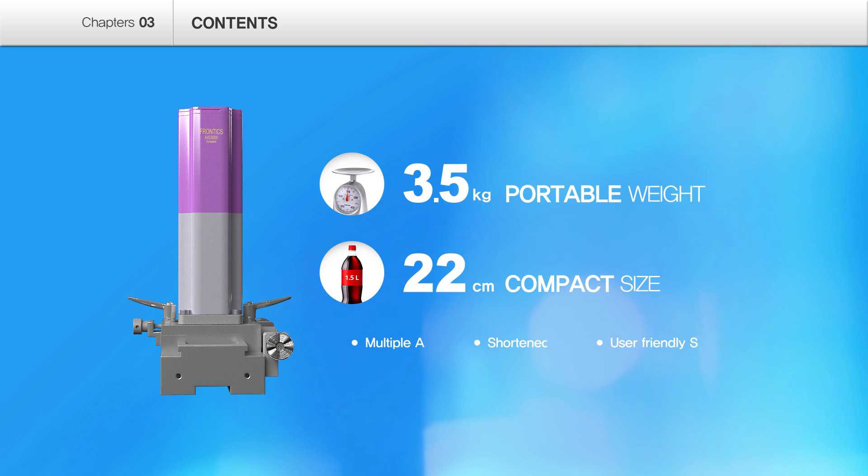AIS 3000 Compact Equipment weighs 3.5 kilograms with 22 centimeters length. It is similar to the size of 1.5 liter cola bottle, and it has different attachments to conduct testing on-site easily with application to tested objects.